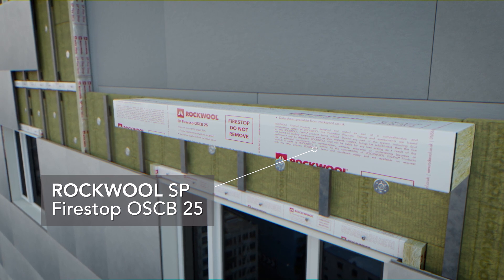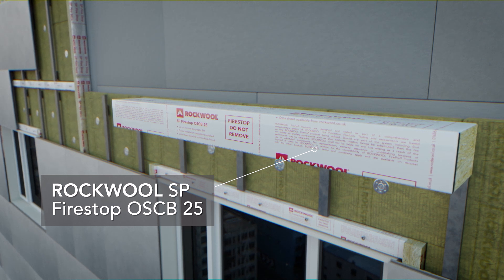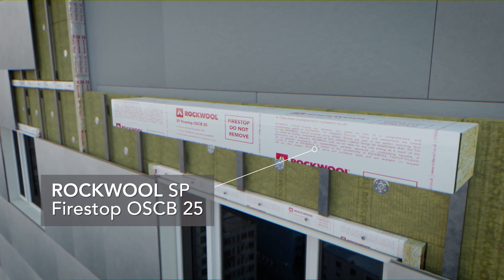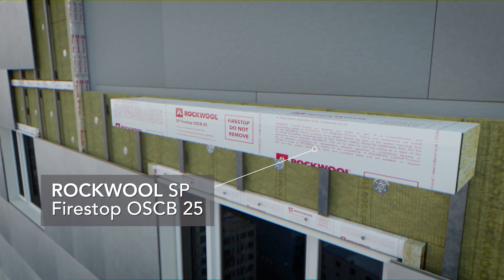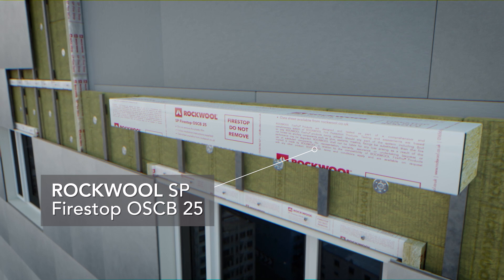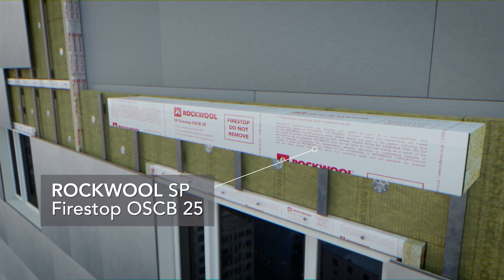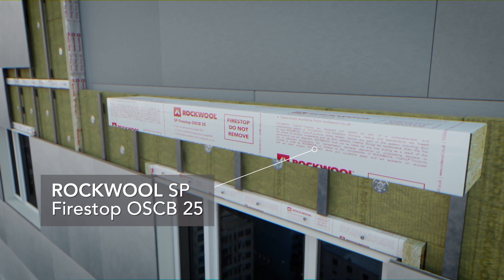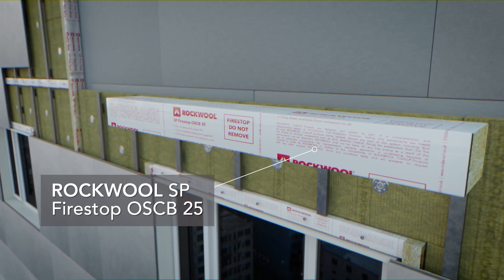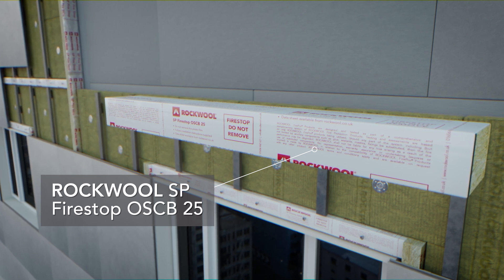OSCB 25 is an open-state cavity barrier suitable for horizontal use in rain screen systems. Designed to partially fill the cavity, the product allows for ventilation and drainage in normal operation. In the event of a fire, the front-facing intumescent strip expands to seal the cavity, preventing the passage of fire and smoke. OSCB 25 allows for a 25mm open airspace.